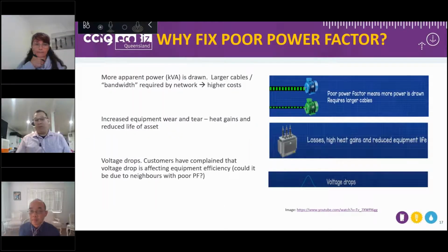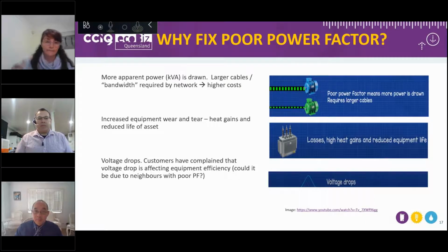Okay, why fix poor power factor? Power factor is, of course, in itself not a bad thing, but it can cause issues on sites. The first one is the cost. If you are on a kVA tariff, like many customers across Southeast Queensland already are, and some customers in regional Queensland have known for a while, the closer your power factor is to 1, the less impact it has on your bill. So there is a direct financial driver to have good power factor.